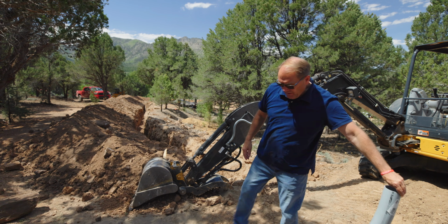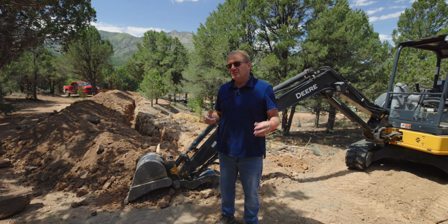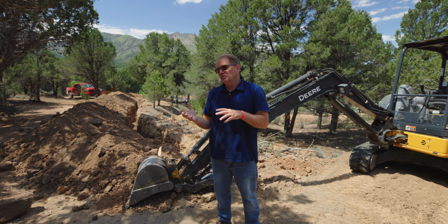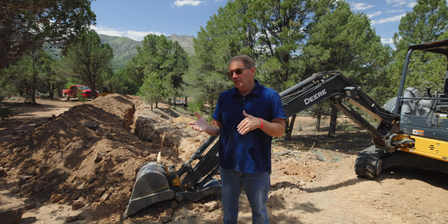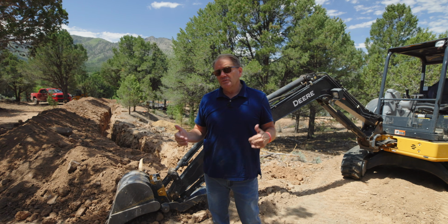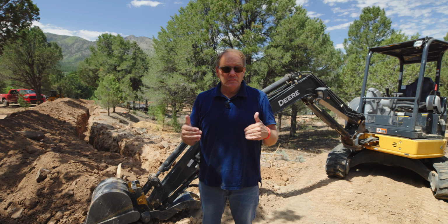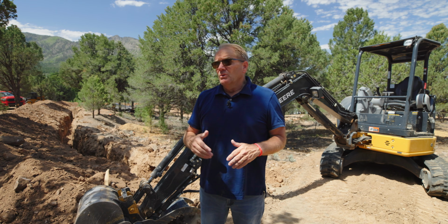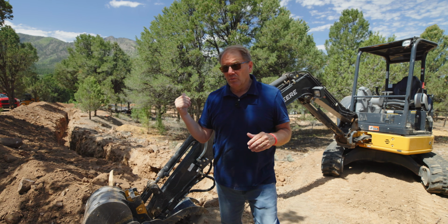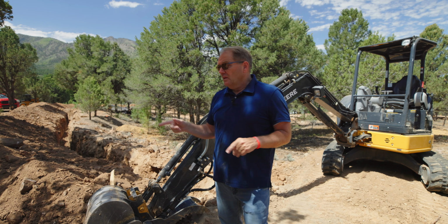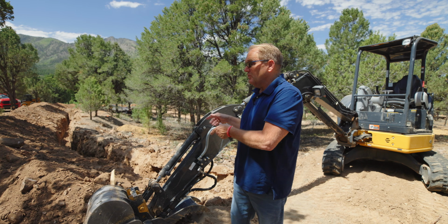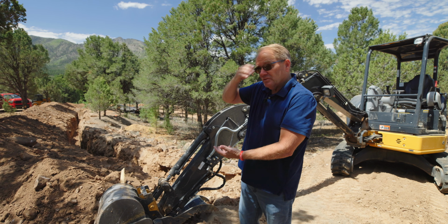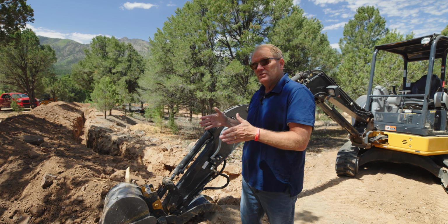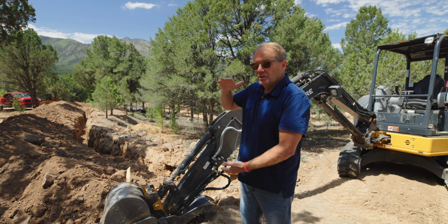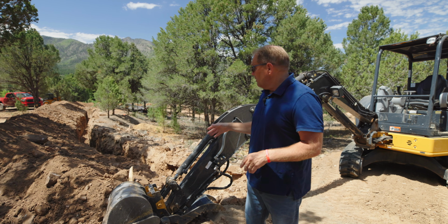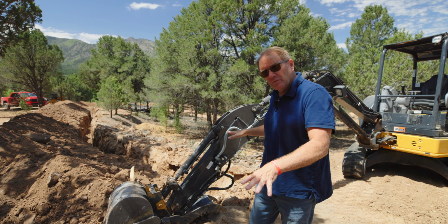Now, some jurisdictions don't recommend it, but it can be done - I'm going to put low voltage cable, which might be future fiber optics that I know is being installed down the road, 12 inches apart in the bottom of the trench. You can put them horizontally or vertically 12 inches apart; either way, we're just going to do it on the bottom of the trench.